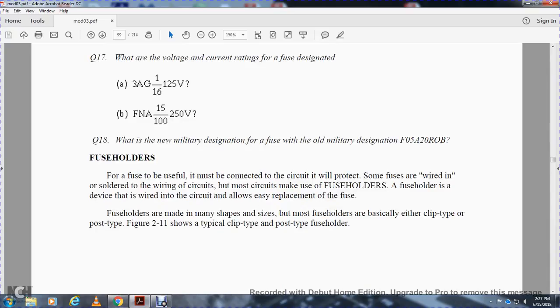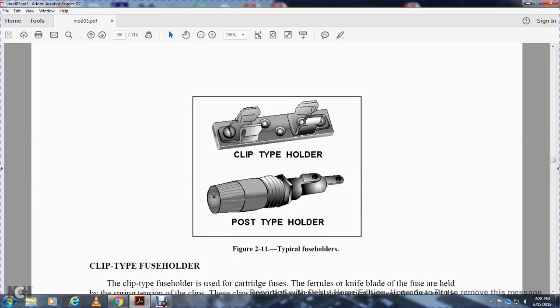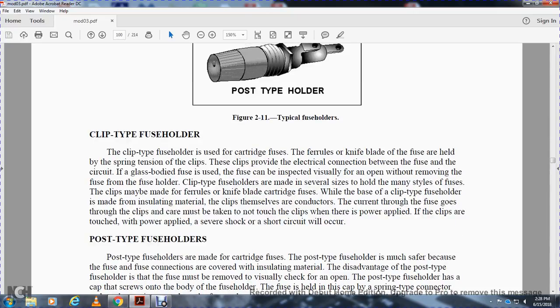Fuse holders: for a fuse to be useful, it must be connected properly in the circuit. A fuse holder is a device that connects the wire into the circuit and allows easy replacement of the fuse. Fuse holders come in many shapes, but most are basically either clip type or post type. Figure 2-11 shows typical clip type and post type fuse holders. The clip type fuse holder holds cartridge tube fuses, knife-blade fuses, and glass-tube fuses with spring tension clips. The fuse can be inspected visually for an open condition without removing the fuse from the holder. Clip type fuse holders are made in several sizes for many types of fuses.